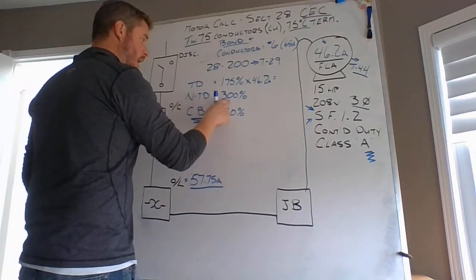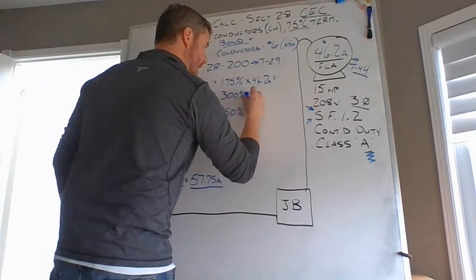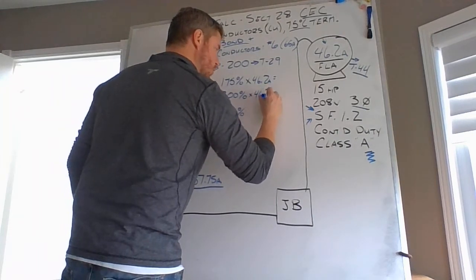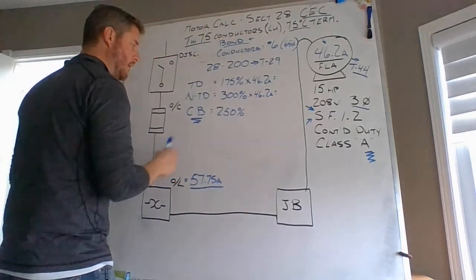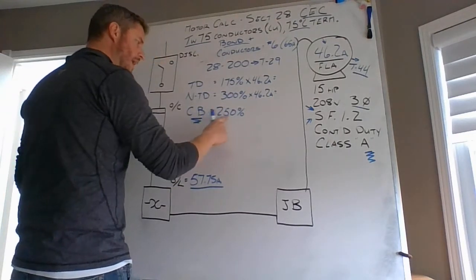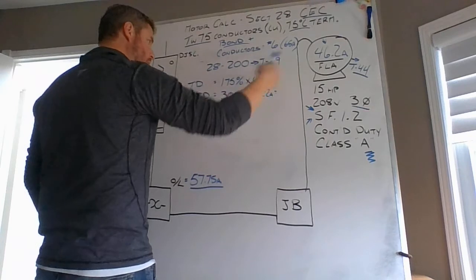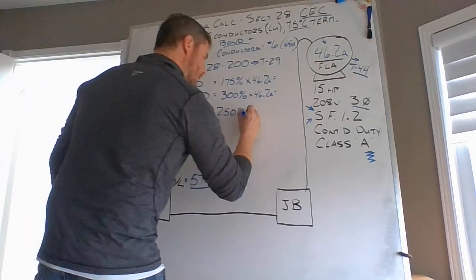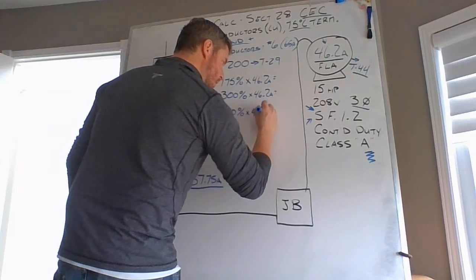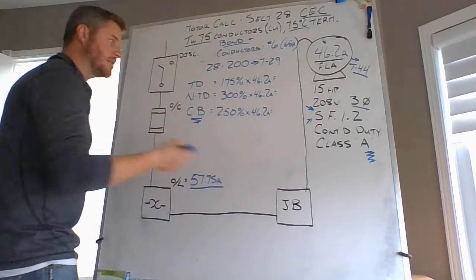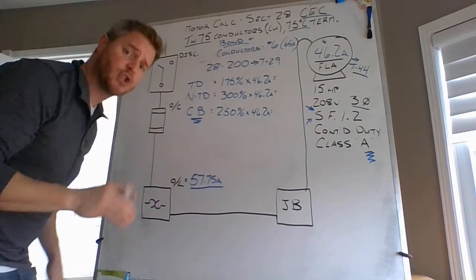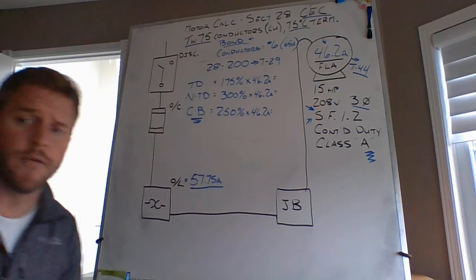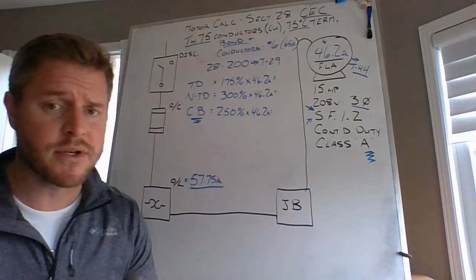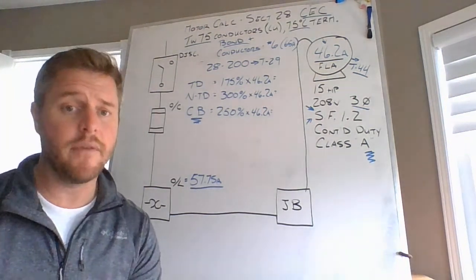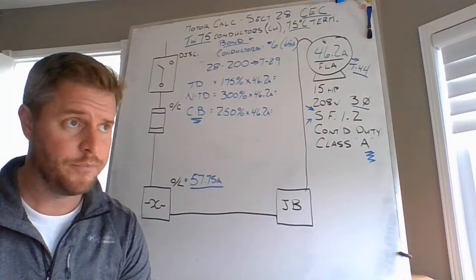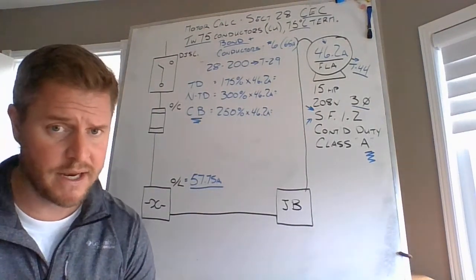Do the same thing with a non-time delay fuse at 300% times 46.2 amps and come up to a maximum installed value. Same thing with a circuit breaker, 250%, the full load current rating of that motor times 46.2 amps to come up to maximum values. Maximum installed values. This is a good time for you to hit pause, just to go back and observe the rules from 28200 and have a look at table 29 when we're looking at overcurrent selection of devices.